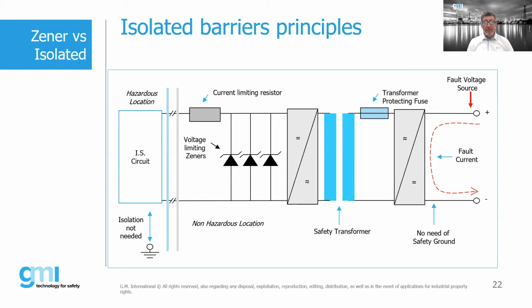And also, Bob, I think, we're talking about safety earlier. In a way, it is a safer solution, because when that safety ground is missing for whatever reason, or it goes above 1 ohm or is disconnected, you are in a dangerous situation. With an isolated barrier, there's basically nothing you can do to render it unsafe other than short it, just put a jumper across it. Right.